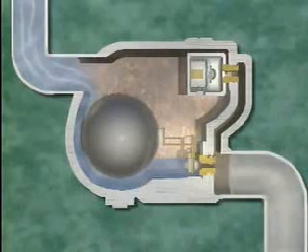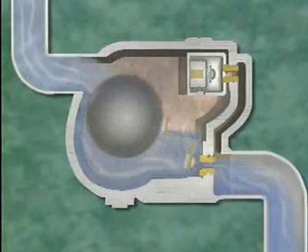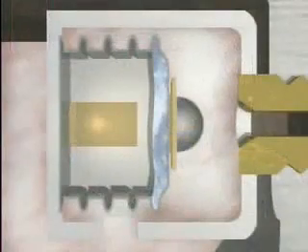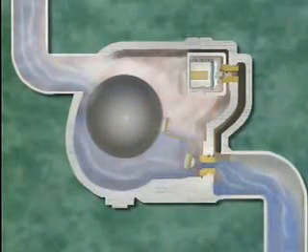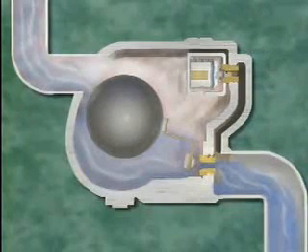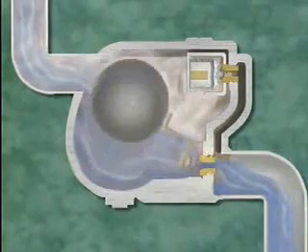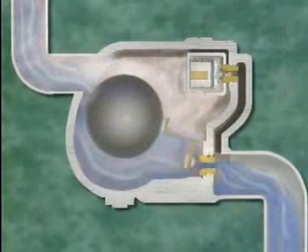As condensate enters the trap, the accumulating condensate lifts the ball-type float attached to the trap's main valve, opening the main valve and allowing condensate to flow through the trap outlet. When steam enters the trap and reaches the bellows, the bellows expands and the vent valve closes. With the main valve open, condensate continues to flow through and be discharged. The changing level of the condensate causes the float to rise and fall, which affects how wide the trap valve opens and how much condensate is discharged.